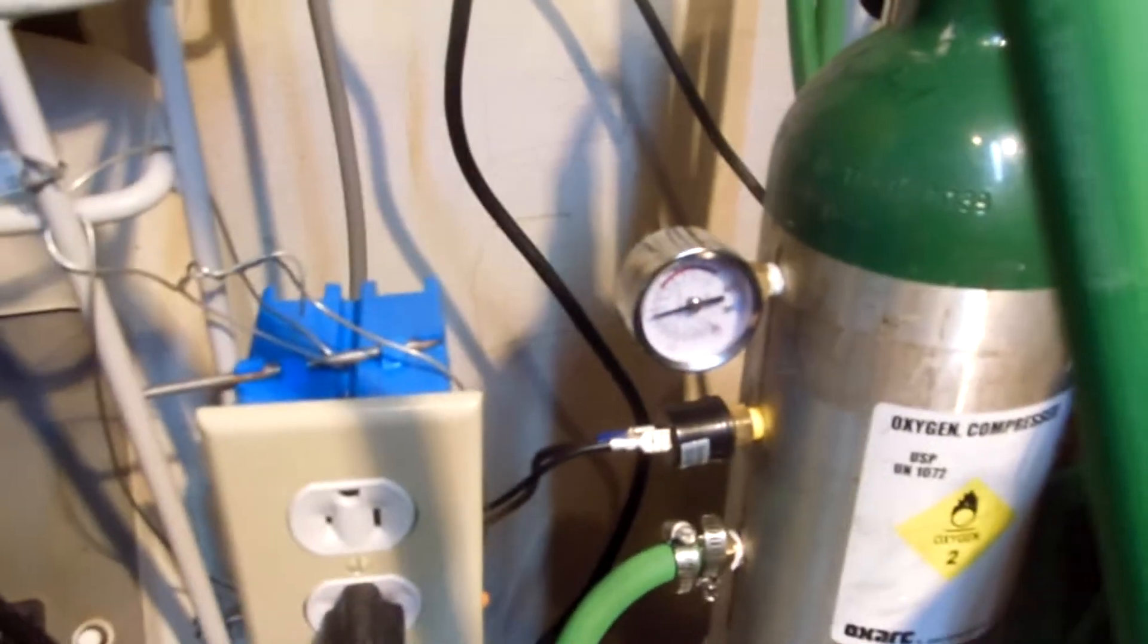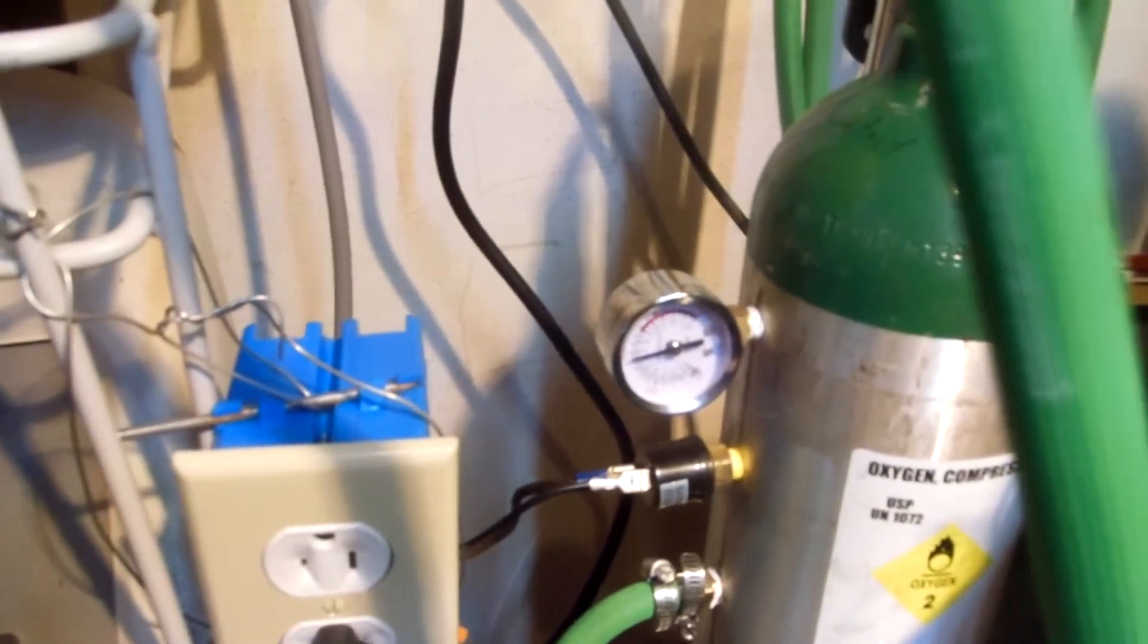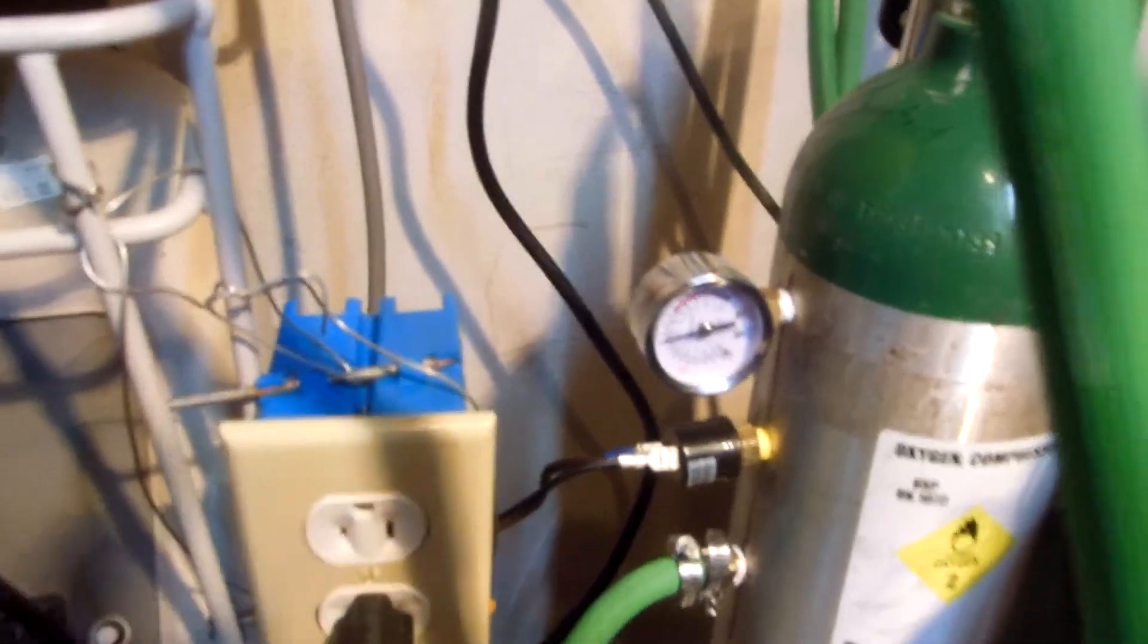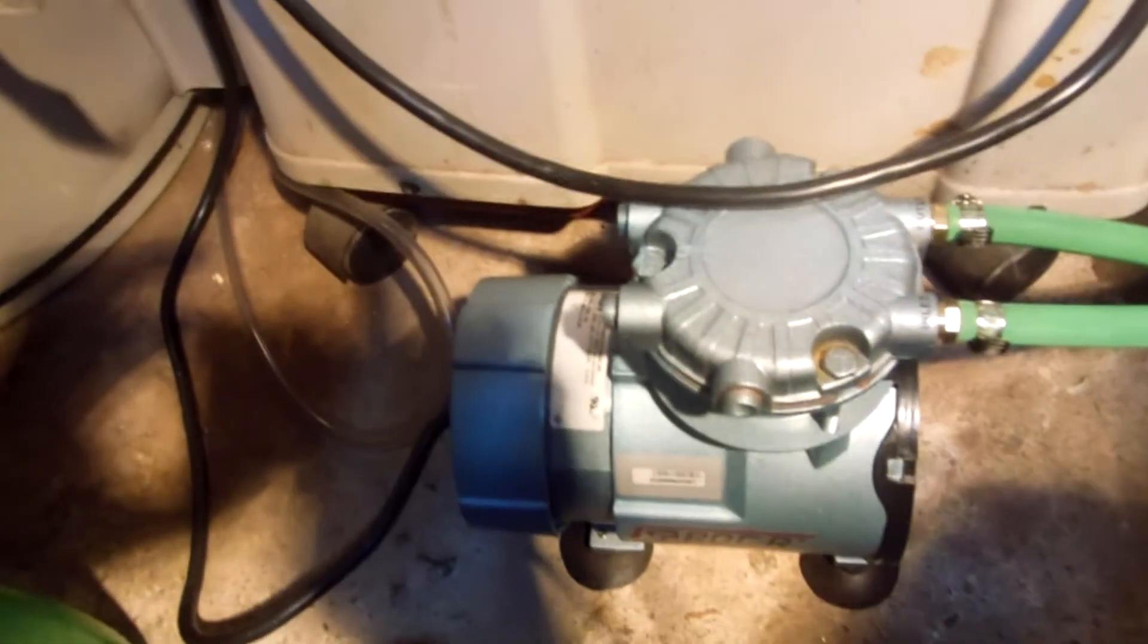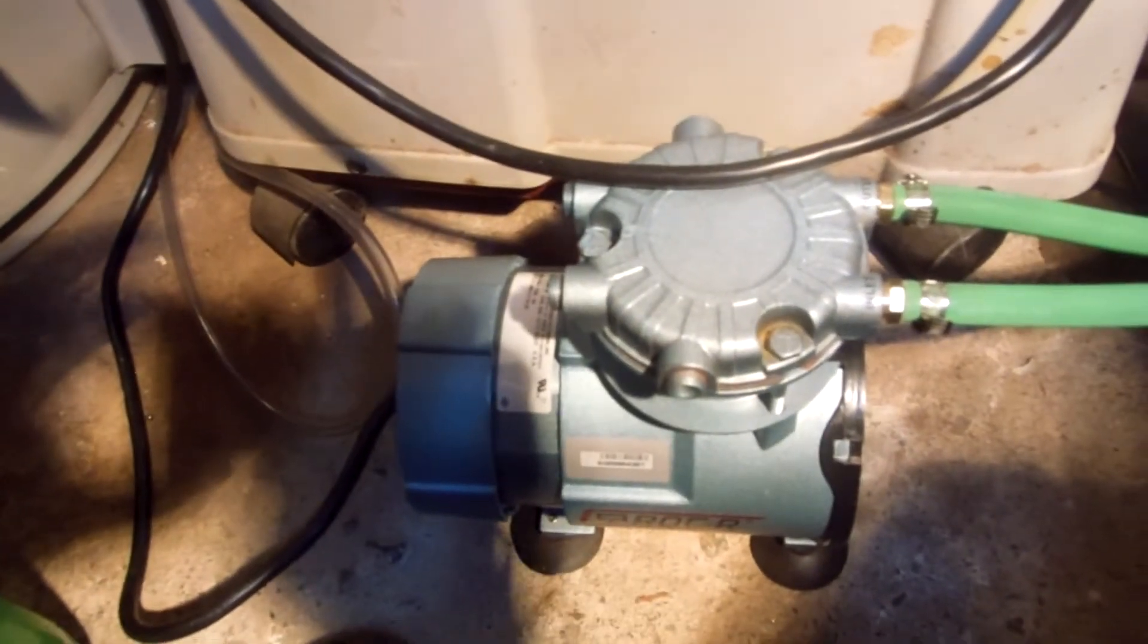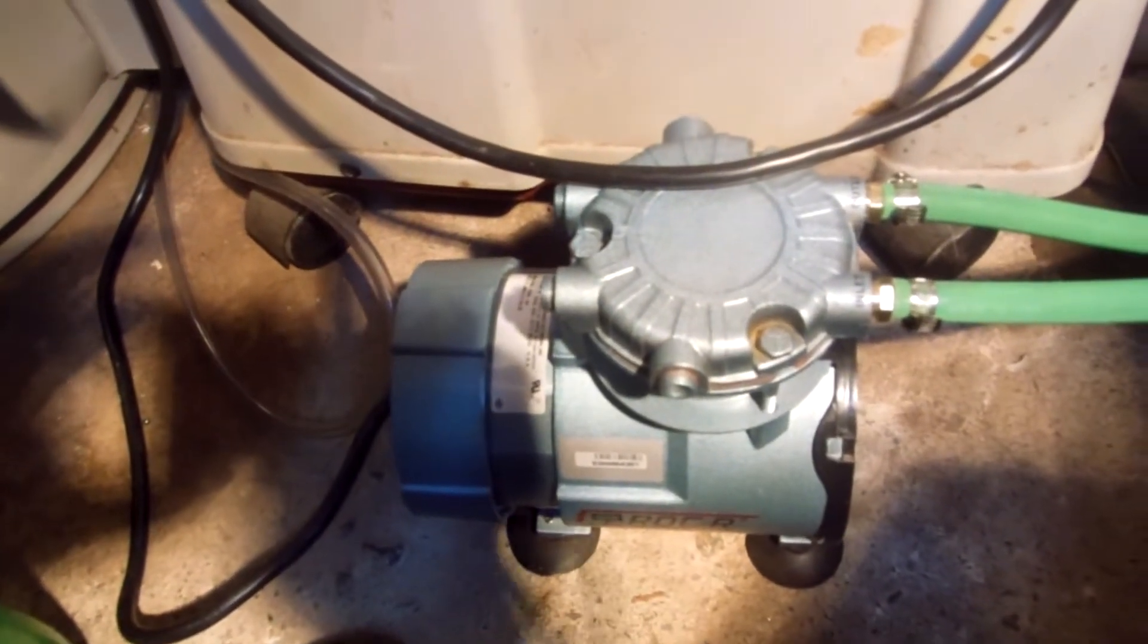When this, if this was to shut off, and if the compressor doesn't restart due to being under a load, I would turn off that valve right there.